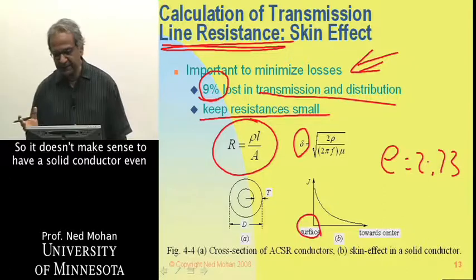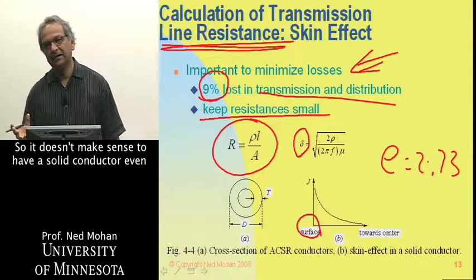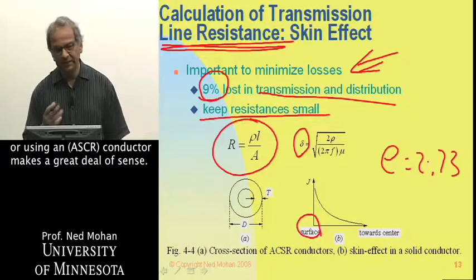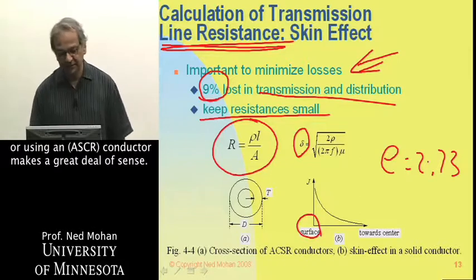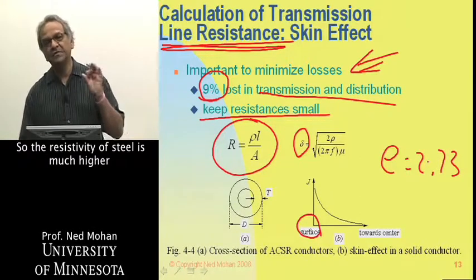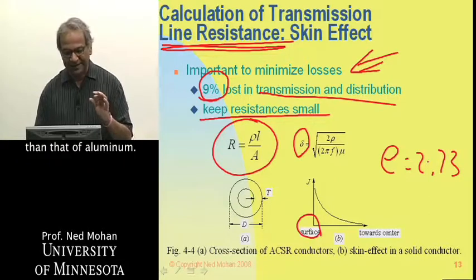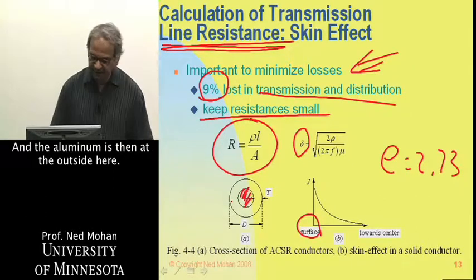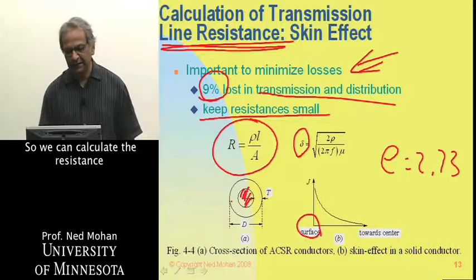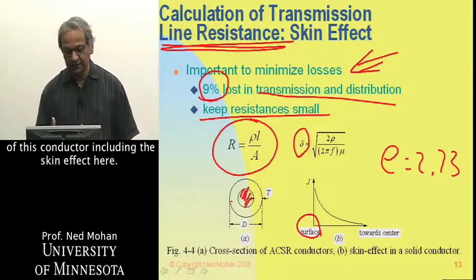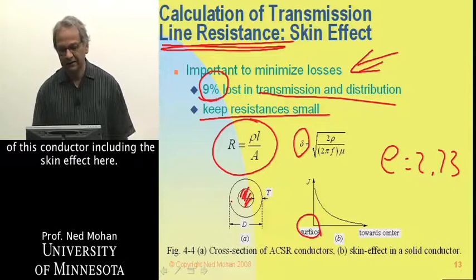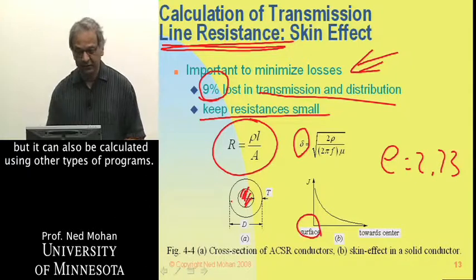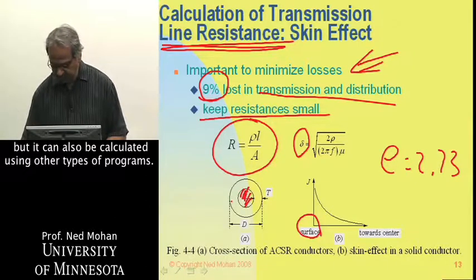It doesn't make sense to have a solid conductor even at 60 Hz due to skin effect, so using an ACSR conductor makes great sense. Since the resistivity of steel is much higher than that of aluminum, we can consider the steel core to be hollow for current-flow purposes, with aluminum on the outside. The resistance of this conductor, including skin effect, is given in tables and can also be calculated using other programs.